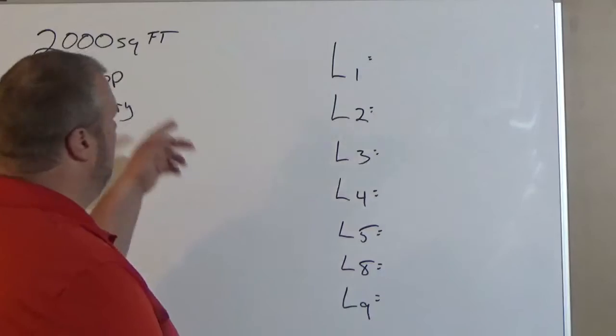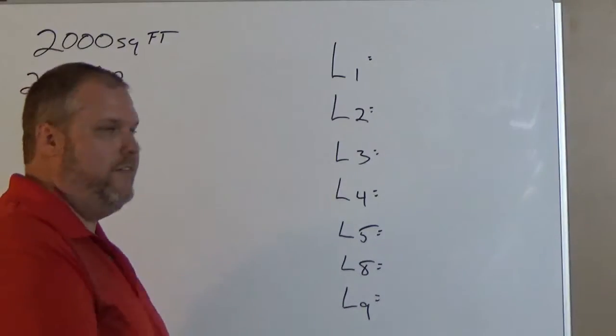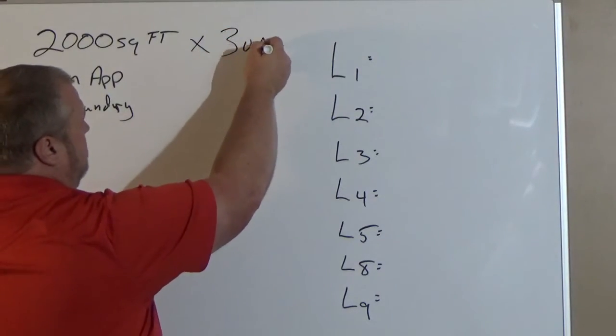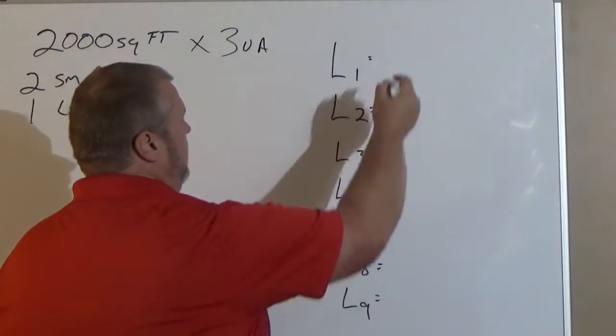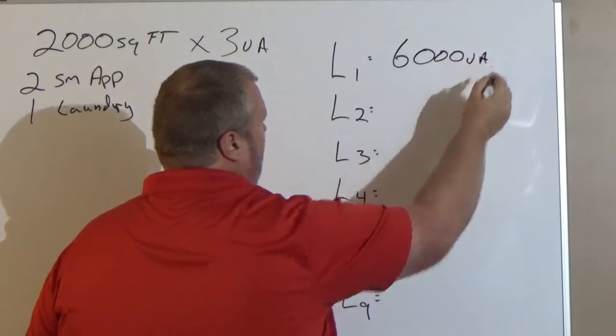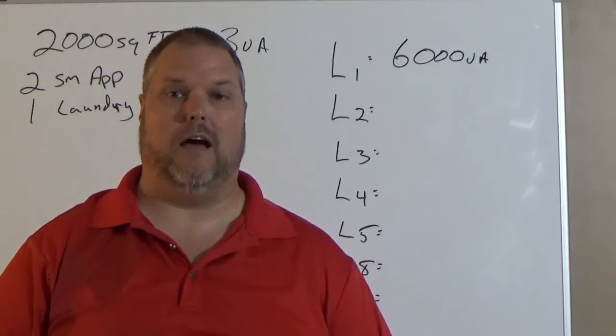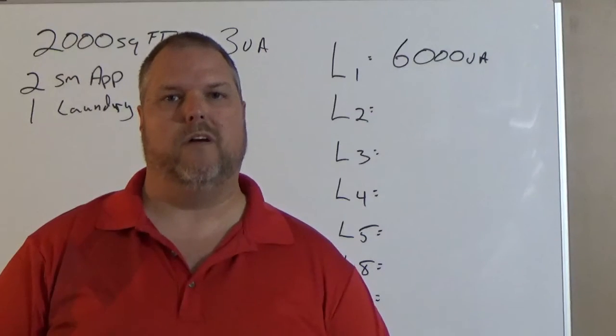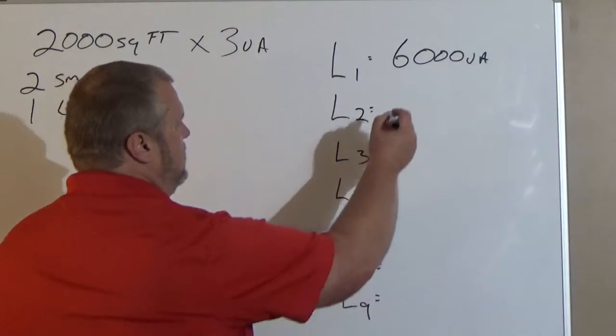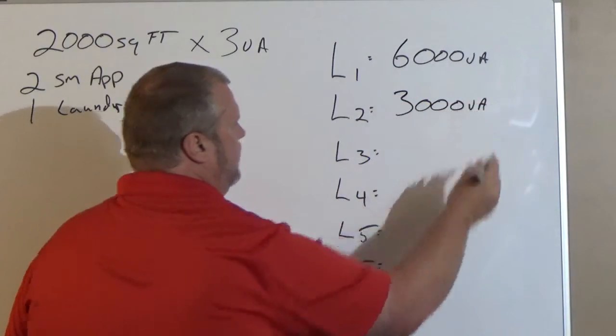First things first, line 1: 2,000 square feet, multiply it by 3 VA, it's going to give us 6,000 VA. 6,000 goes in line 1. Line 2 is our small appliance line. We're doing it to code, we know we have 2. So we're going to put 3,000 VA in line 2.